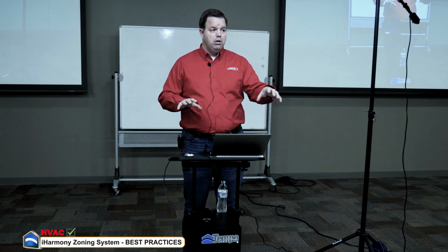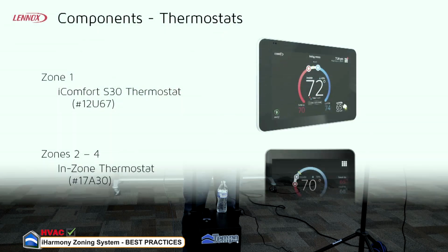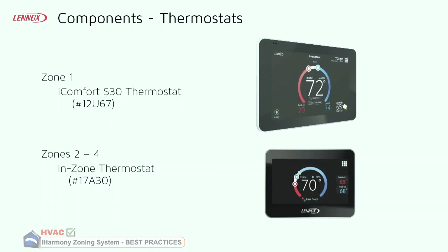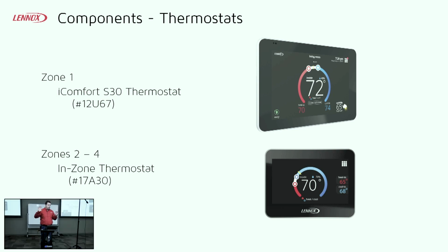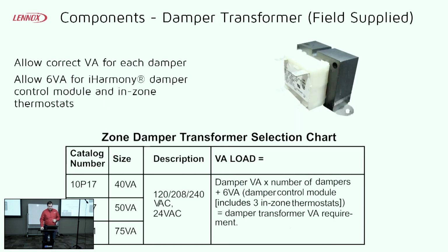Because if you set them all just powered down on a table, looking at the face of them, you wouldn't be able to tell them apart. But when you flip these over, the zone sensors just have a 4-wire connection. Good, because they're communicating, they're only designed to talk to the zone board, and that's all they will do. And you can't use a ComfortSense 7500 or M30 as a substitute. So the damper transformer, it's going to be field supplied.